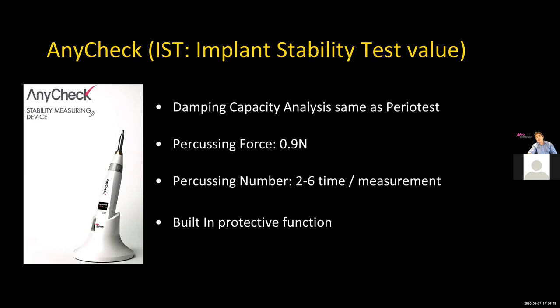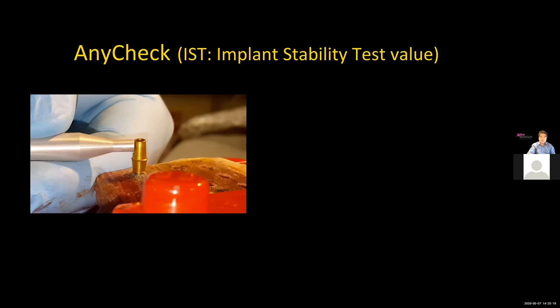Neobiotech, about five years ago, revisited and upgraded damping capacity analysis. The percussing force was decreased 30%, and the number of hits is now two to six times: if IST is more than 60, it hits six times; if less than 60, only two times. It also has a built-in protective function — if the implant shows dangerous mobility it gives you a warning sign.